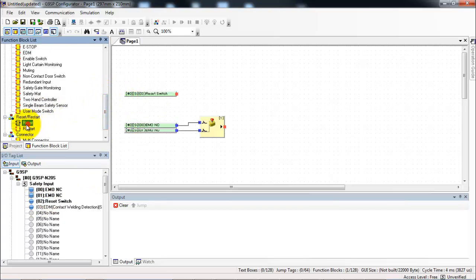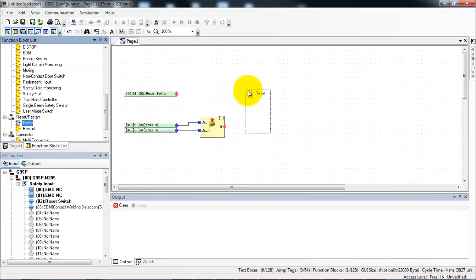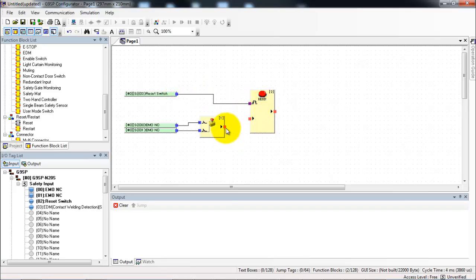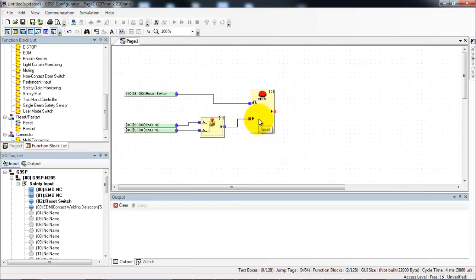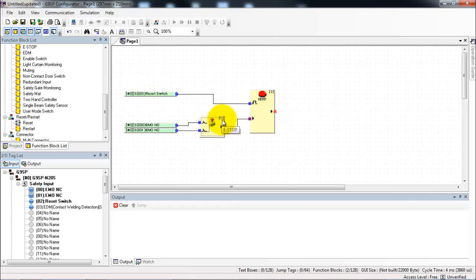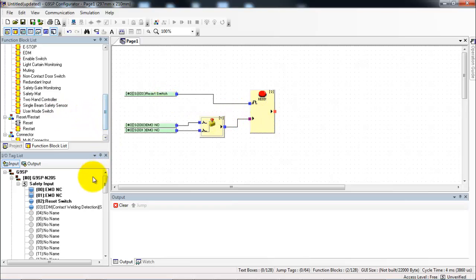Next I need to put in my reset switch. So when the reset switch is toggled I want to allow my system to start back up again. So I'll wire the reset switch into the reset input of the reset function block. And the output enable from the e-stop onto the input of the reset. So this acts kind of like a latching circuit. If the e-stop circuit is good and the reset switch is pressed it allows power to go through. Once the e-stop drops out it will stay off until the reset is toggled again.